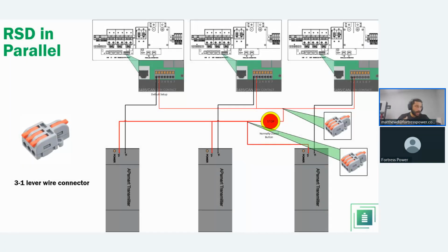If you're doing rapid shutdown in a parallel setting, what we recommend is these 3-to-1 lever wire connectors, and you can get these on Amazon pretty cheap. I think they're about $10, and they include about 10 of those. You'd only be using 2 essentially. But you're basically putting each rapid shutdown in parallel with the inverter, right? So from pin number 1, negative, you're going to land on the negative of the AP Smart transmitter. And then from the positive, you're going to put it in parallel on the rapid shutdown button.